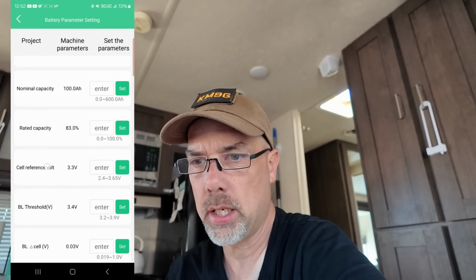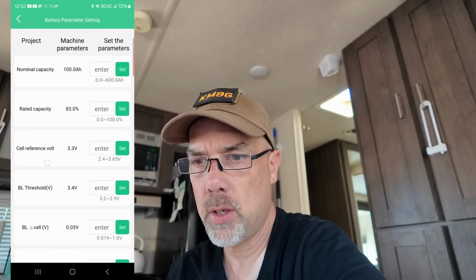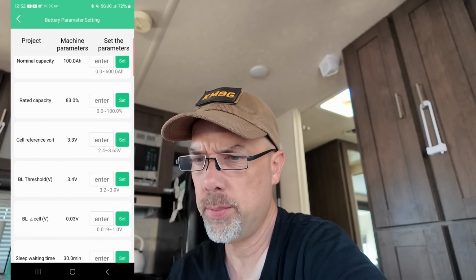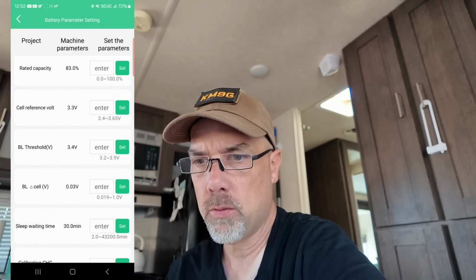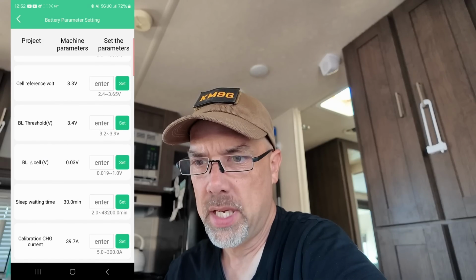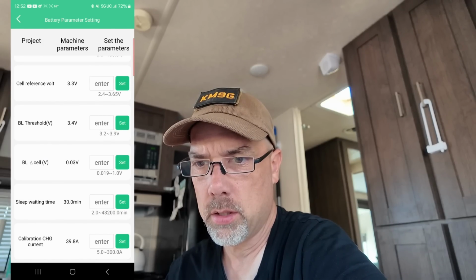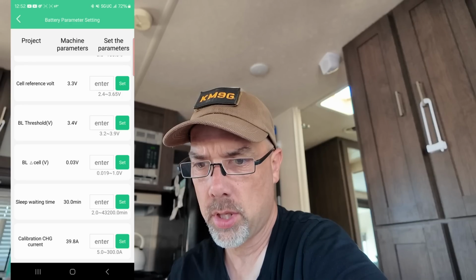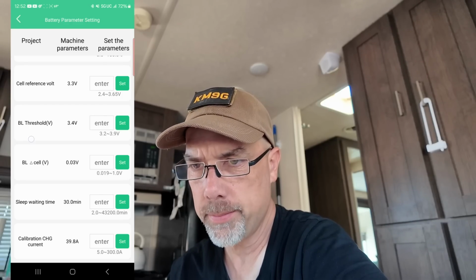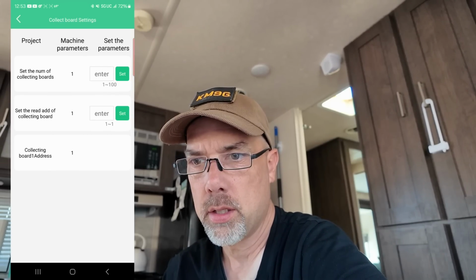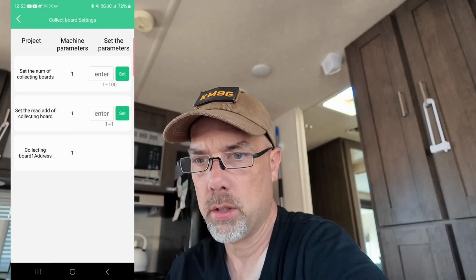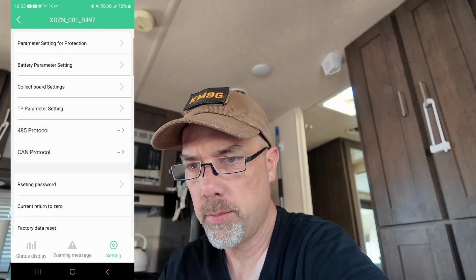Battery parameter setting: nominal capacity 100 amp hours, rated capacity 83%, interesting. Cell reference voltage 3.3, BL threshold 3.4, BL cell 0.03, sleep waiting time 30 minutes. Okay, awesome. Collect board settings - set the number of collecting boards to 1. There's some really neat stuff in here.